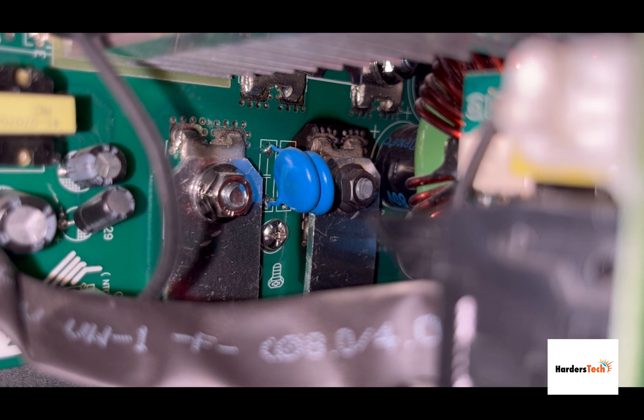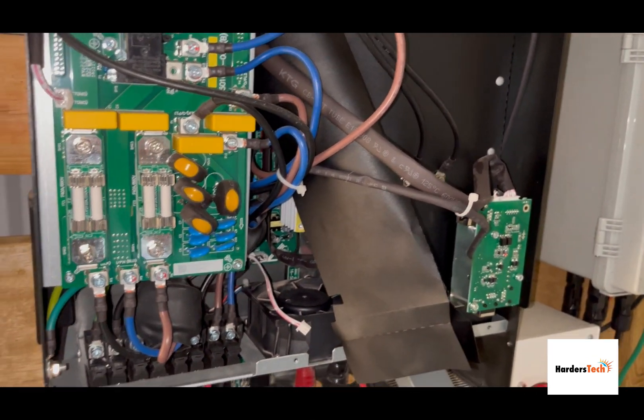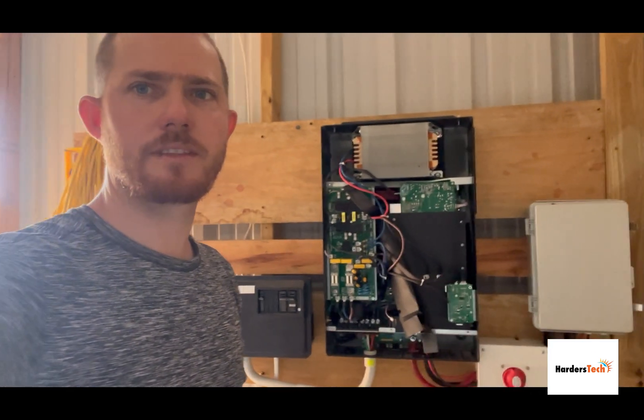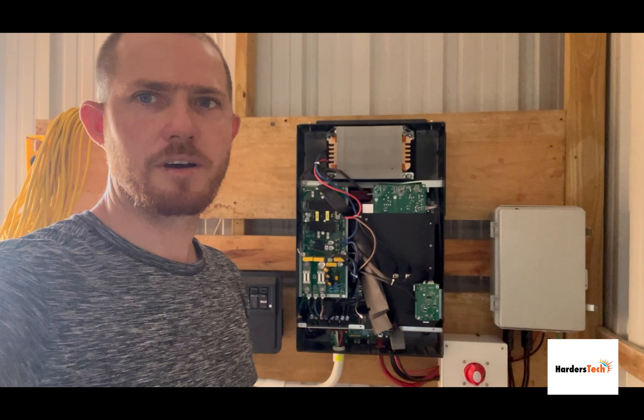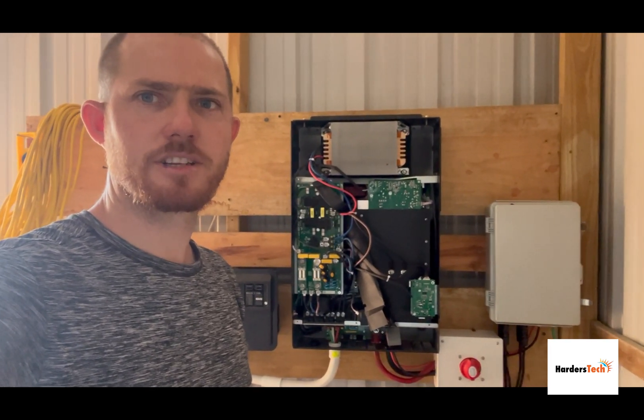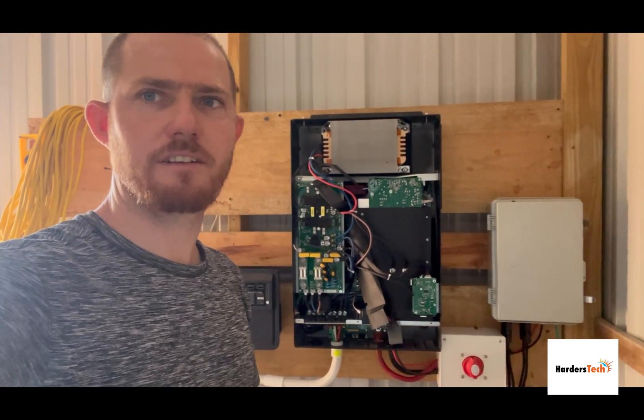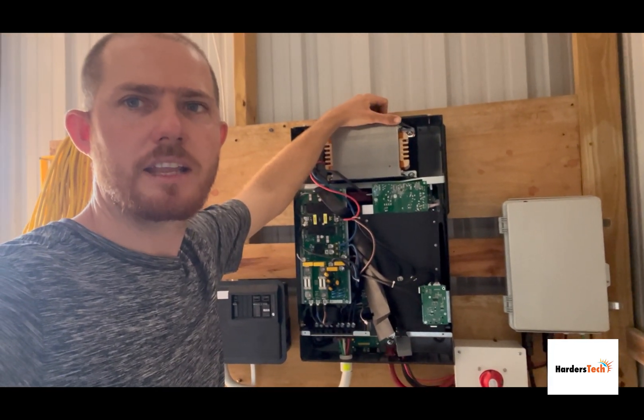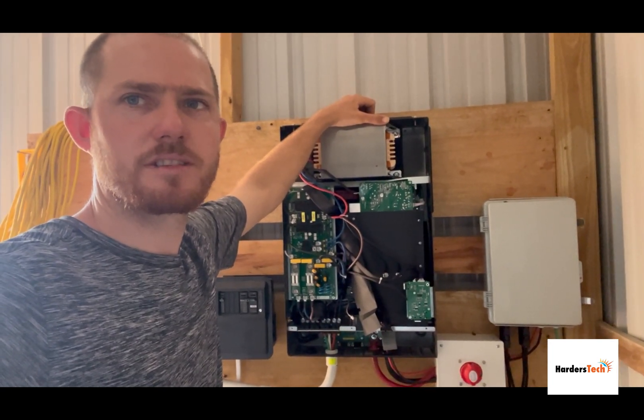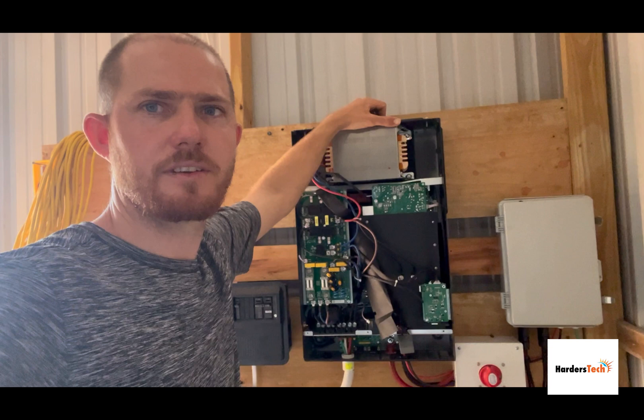This battery terminal is simply not built strong enough for this 6 kilowatt inverter. The manufacturer needs to fix that if they want to sell these units. It's a nice unit and works fine otherwise, but there's an issue with this model. I spoke to a technician who fixes inverters and he told me he tried to fix one of these units before and it just didn't work, so it's better I just replace this one.